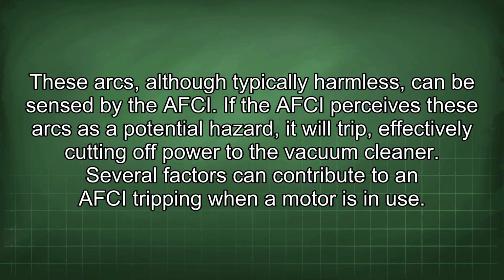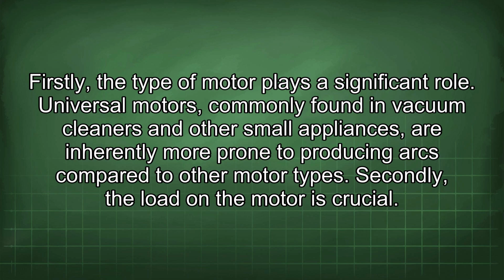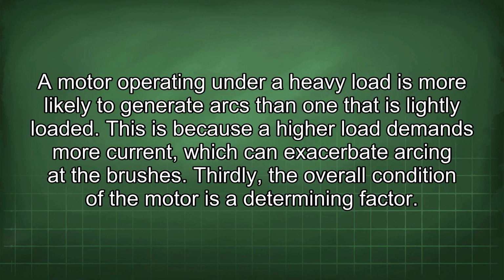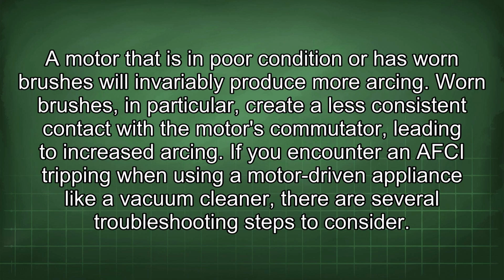Several factors can contribute to an AFCI tripping when a motor is in use. Firstly, the type of motor plays a significant role. Universal motors, commonly found in vacuum cleaners and other small appliances, are inherently more prone to producing arcs compared to other motor types. Secondly, the load on the motor is crucial. A motor operating under a heavy load is more likely to generate arcs than one that is lightly loaded. This is because a higher load demands more current, which can exacerbate arcing at the brushes. Thirdly, the overall condition of the motor is a determining factor. A motor that is in poor condition or has worn brushes will invariably produce more arcing. Worn brushes, in particular, create a less consistent contact with the motor's commutator, leading to increased arcing.